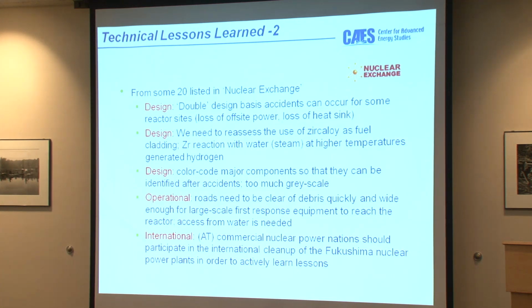But the plant is not sitting elevated up in the air. It's sitting on the ground. And in Tokyo, if you look at the incidence of large earthquakes, 7.0 or larger, they've had like 5 or 6 in the last 500 years in recorded history. So 5 in 500 years says the probability of a large earthquake followed by a tsunami is more like 1 in 100. Even though you build the reactor to be 1 in 100 million for a severe accident, the land it's sitting on has a much higher probability for something happening. So we need to rethink that process.